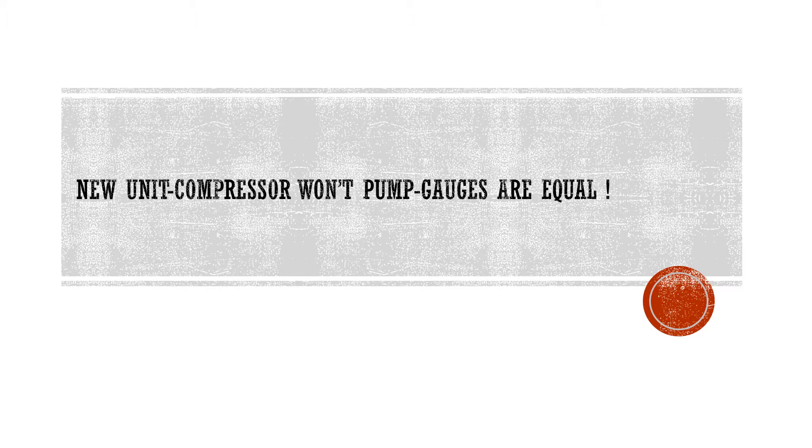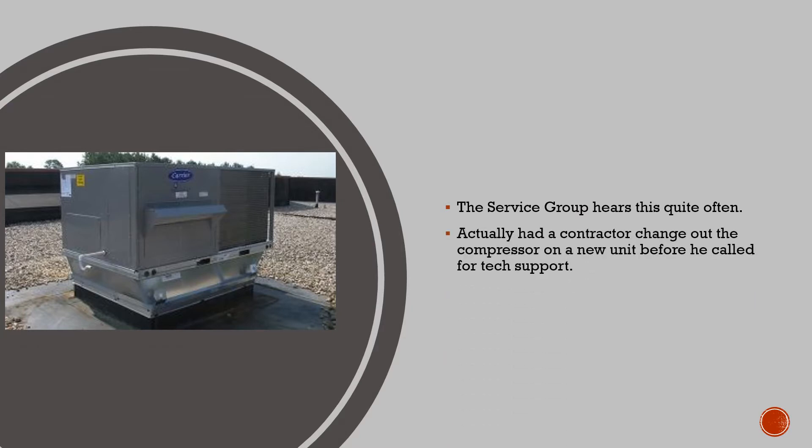I have a new unit. Compressor won't pump, gauges are equal - must be another bad compressor. The service group hears this quite often. We actually had a contractor change out the compressor on a new unit before he called for tech support.